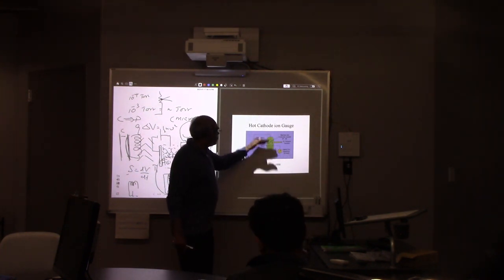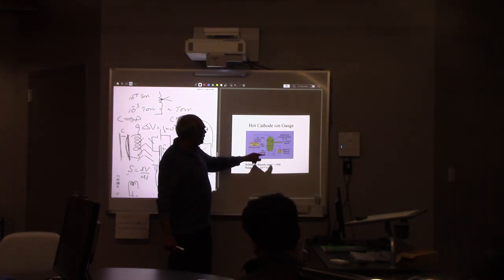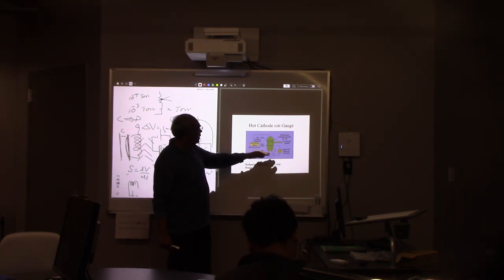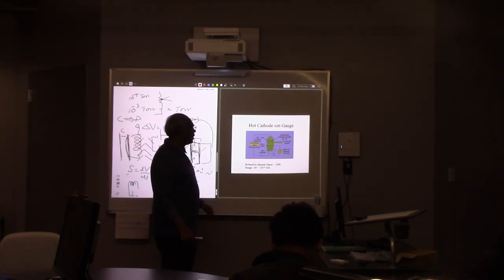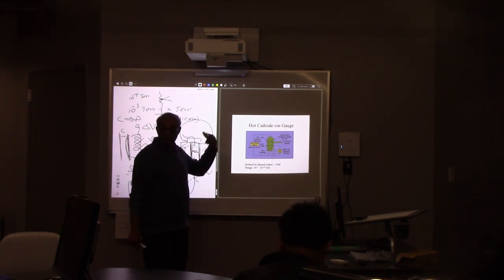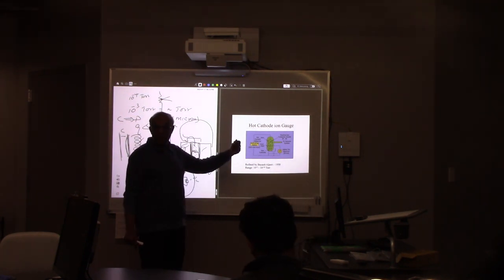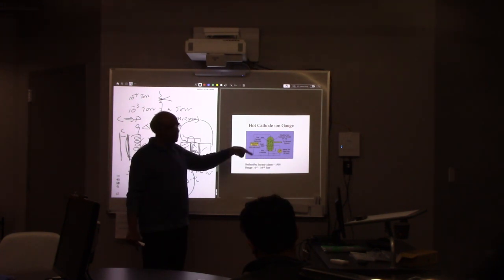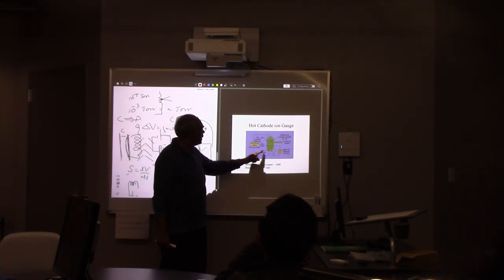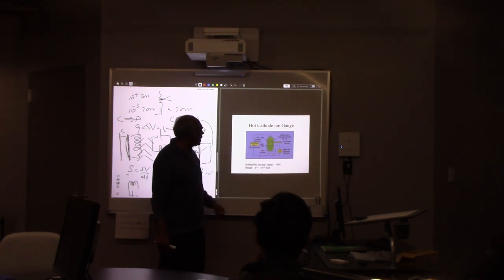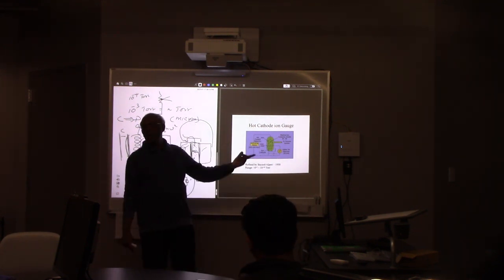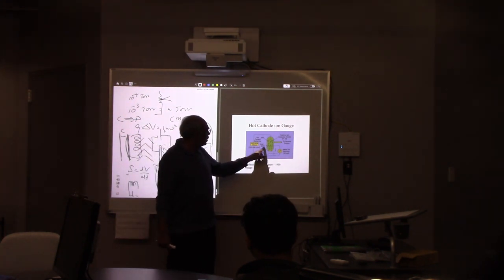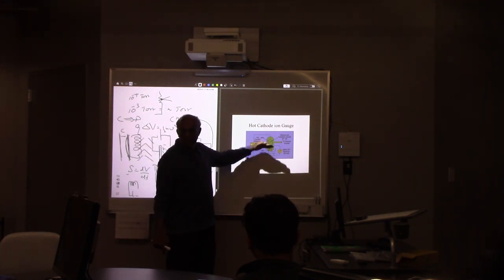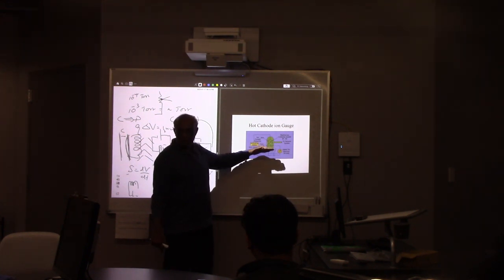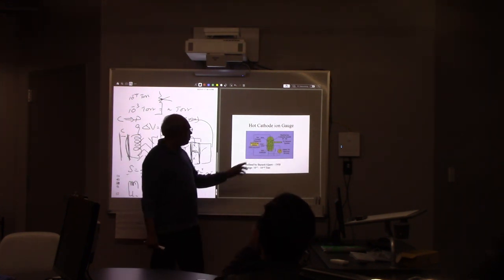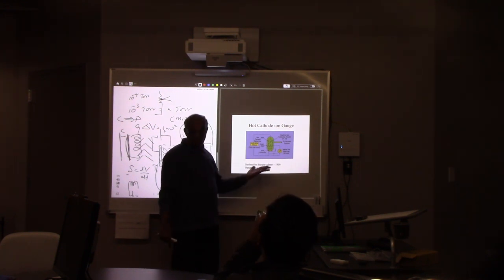So with these two, basically, you attract these electrons more efficiently. That's a very simple thing, right? You just thermionically emit electrons that will ionize the charges, and then you just measure the ion gauge current. You don't have to apply really high voltage, only enough voltage to guide the electrons. Is that it? So just by heating, this is called thermionic emission, right?